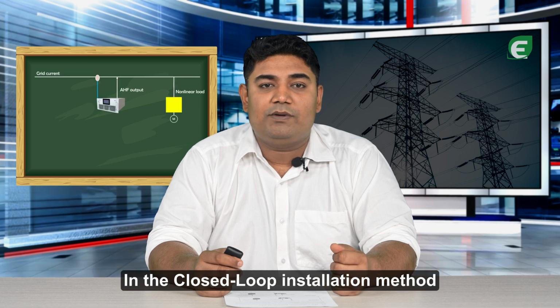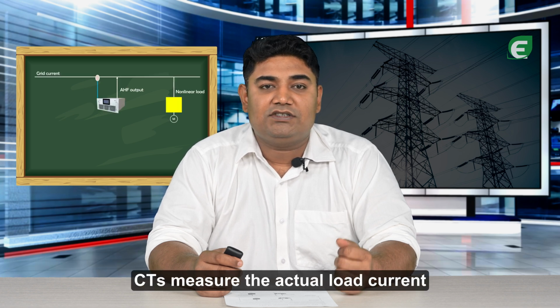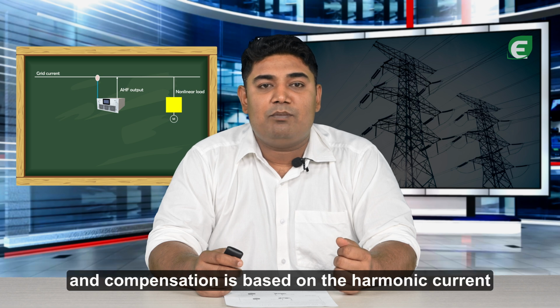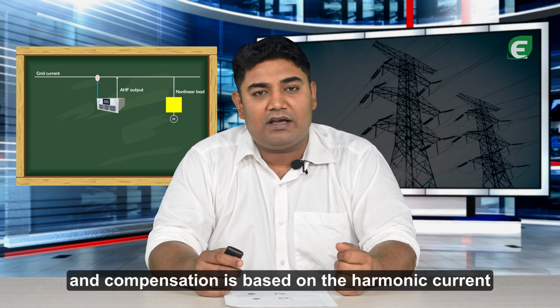In the closed loop installation method, CTs measure the actual load current and the compensation is based on the harmonic current detected at the load. The advantage of this method is higher compensation accuracy and faster dynamic response, but sometimes installation can be more complex. This method is suitable for on-site compensation of harmonics for precision loads.